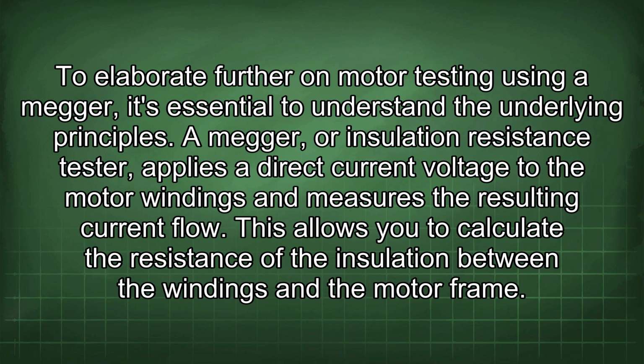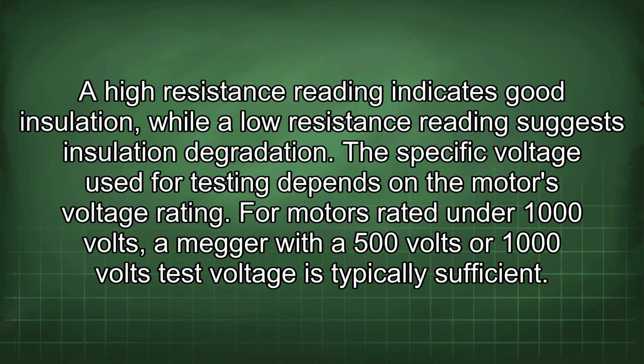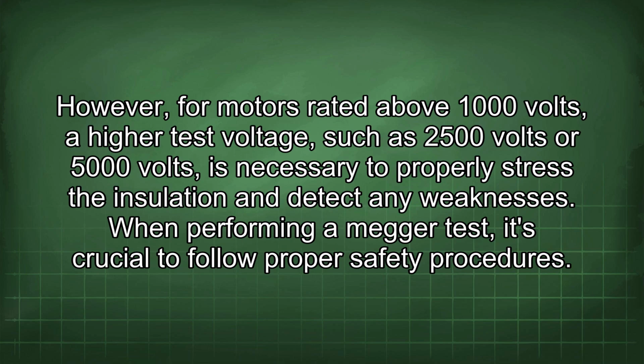A Megger, or insulation resistance tester, applies a direct current voltage to the motor windings and measures the resulting current flow. This allows you to calculate the resistance of the insulation between the windings and the motor frame. A high resistance reading indicates good insulation, while a low resistance reading suggests insulation degradation. The specific voltage used for testing depends on the motor's voltage rating. For motors rated under 1000 volts, a Megger with a 500 volts or 1000 volts test voltage is typically sufficient. However, for motors rated above 1000 volts, a higher test voltage, such as 2500 volts or 5000 volts, is necessary to properly stress the insulation and detect any weaknesses.